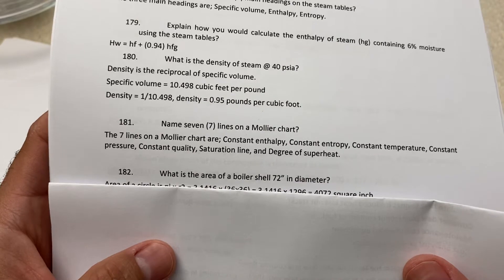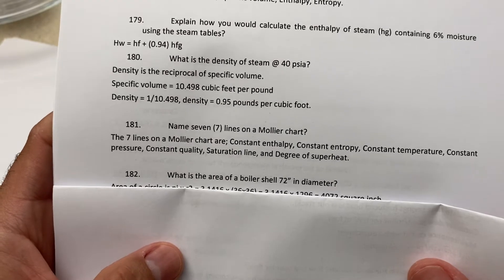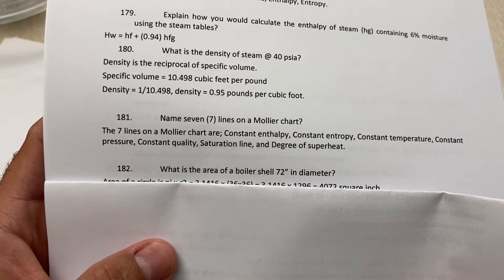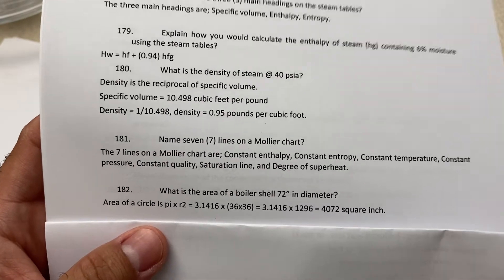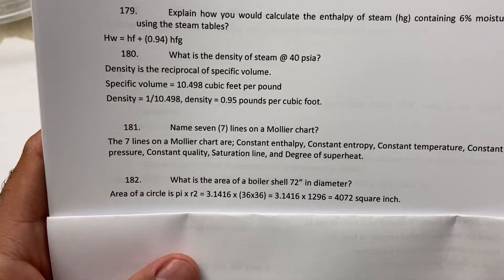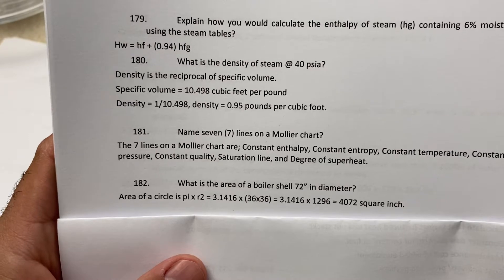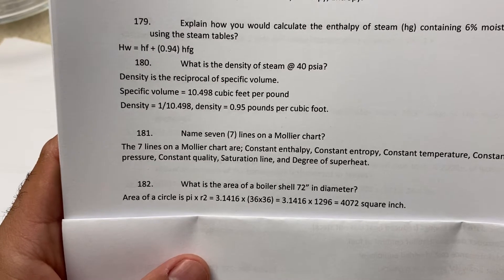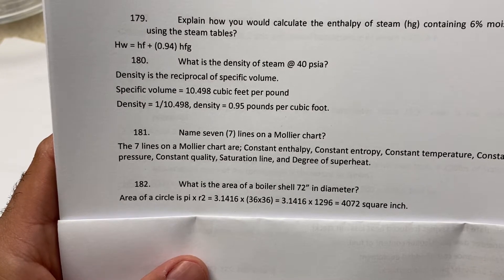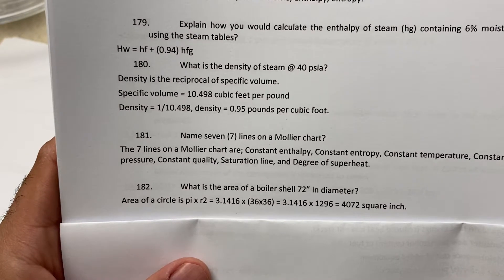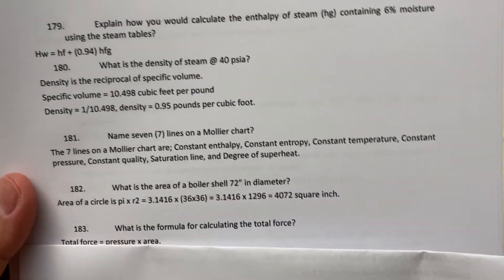What is the area of a boiler shell 72 inches in diameter? The area of a circle is pi times radius squared. Pi is 3.1416, and the radius is 36 inches, so 3.1416 times 36 times 36 gives that specific boiler an area of 4,072 square inches.